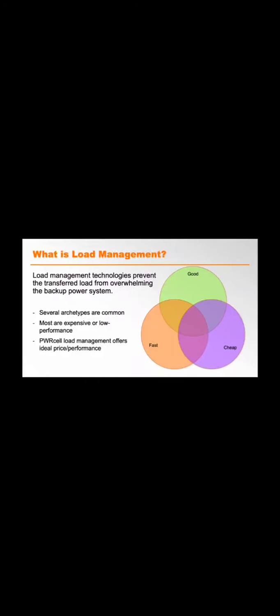So now that we know some about why load management is important, let's talk about what it is. Broadly speaking, load management technologies prevent the circuits from drawing more than the backup power system can serve. Even though some loads will be prevented from running simultaneously, a good load management system will not prevent any loads from being run during the course of the outage, okay? Unless, of course, that load really has no business being on an outage. You know, hot tubs, pools, that kind of thing might want to be prevented from running completely. But existing load management solutions are generally not perfect and fall into a couple of broad categories.